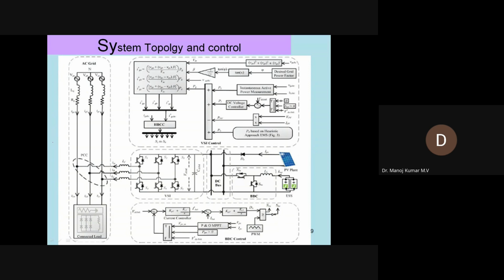But here the advantage is the power factor as seen by the grid can be exactly controlled by controlling tan phi, and the additional modification here is the computation of the PV and how you are controlling the timing for battery charging as well as discharging.